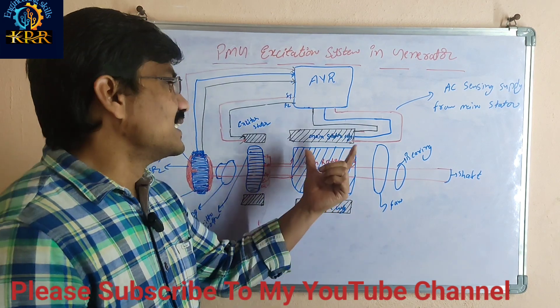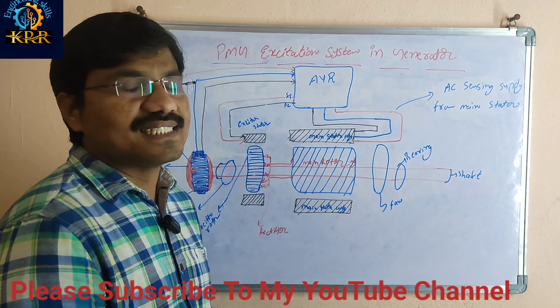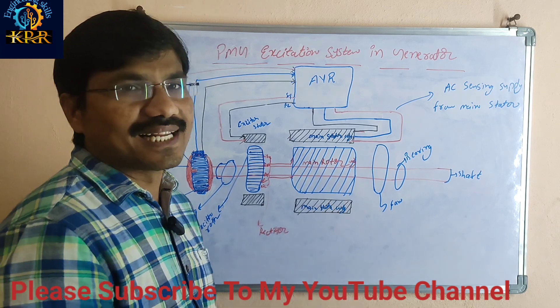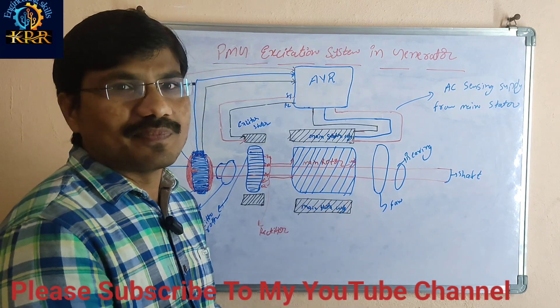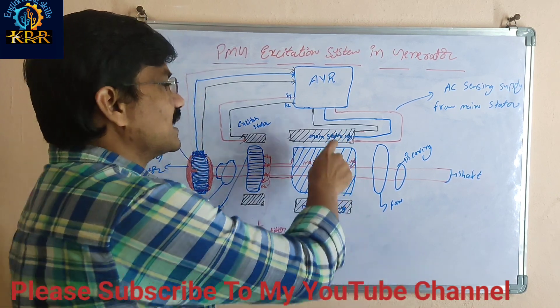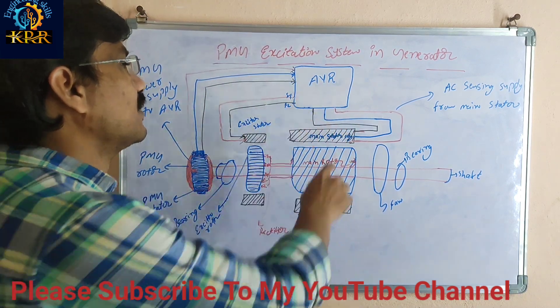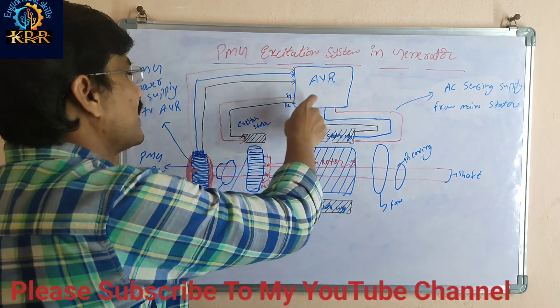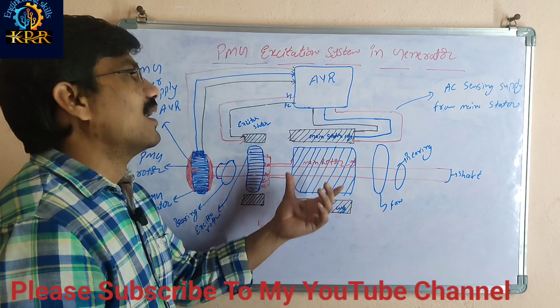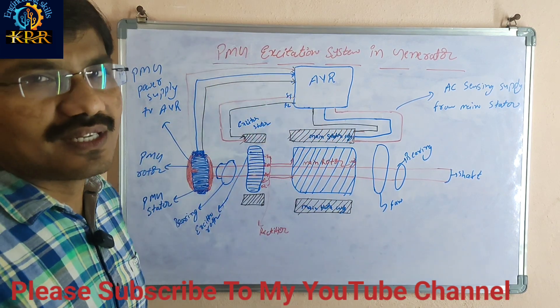The disadvantage of the self-excitation system is that when sudden load variation happens — if the load rises suddenly or a voltage dip occurs — the stator generates low voltage. This low voltage is supplied to the AVR, and the AVR cannot provide proper excitation current to the rotor.